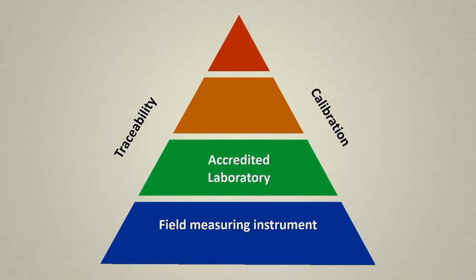Once the calibration value, curve, or table, along with the corresponding uncertainties are known, if it's outside a specific tolerance range, the measurement can be corrected by adjusting my instrument. It's also important that the measurement standards and procedures of these laboratories are calibrated and accredited by the corresponding national institutes, who handle the national or primary measurement standard.